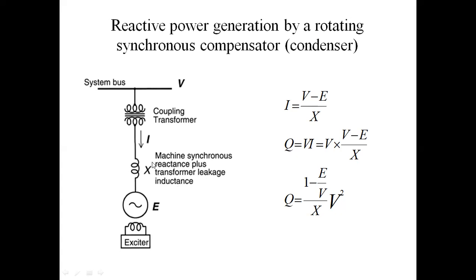The synchronous machine reactance is here, representing the synchronous machine. This is the synchronous machine stator and this is the synchronous machine rotor. The field is excited separately by a DC supply. E is the synchronous machine generating voltage; V is the transmission line voltage. The current I in the compensator circuit is given by the formula: I = (V − E) / X, where V is the system transmission line voltage, E is the synchronous compensator generating voltage, and X is the reactance — machine synchronous reactance plus transformer leakage reactance.